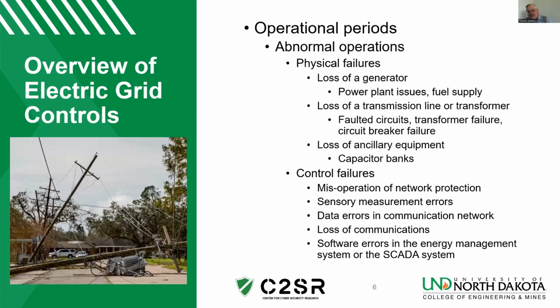In abnormal operations, we experience loss of generation, loss of transmission or transformer, or any of our auxiliary pieces of equipment. Equipment does age, it does fail. Weather events and other outside events take place that cause failures to occur. And those are amongst the physical failures. We do experience a number of control failures. We've talked a little bit about network protection. Misoperation of relays is not uncommon. It does occur on a regular basis.